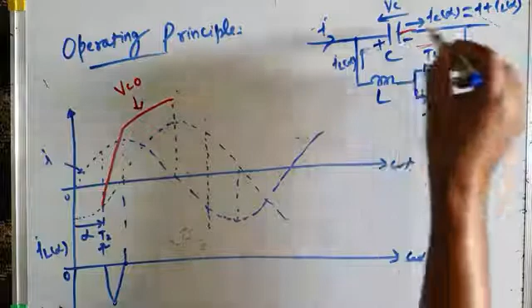Now, negative half cycle of current is there. What is voltage? This is the negative half cycle of current. What is voltage? You can see, this is current, negative half cycle, and this is voltage. Voltage is positive. Positive voltage means your capacitor is charged with this polarity. So therefore, if you want to turn the TCR on, current has to flow in this direction because the capacitor has to discharge. It's with this polarity, positive polarity. And which thyristor switch of this bidirectional switch has to be turned on for making current flow in this direction? T1 has to be turned on. So here the firing pulse will be given to thyristor T1. So T1 will quickly turn on, the capacitor will quickly discharge and then recharge with negative higher voltage.